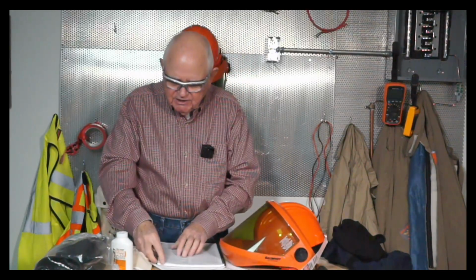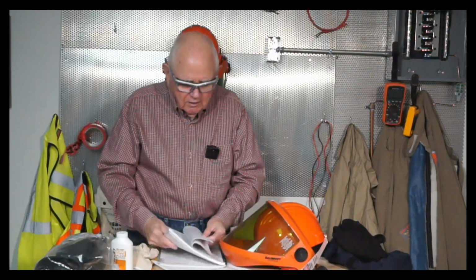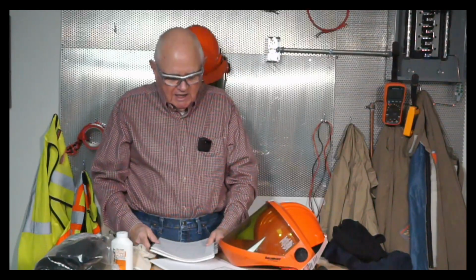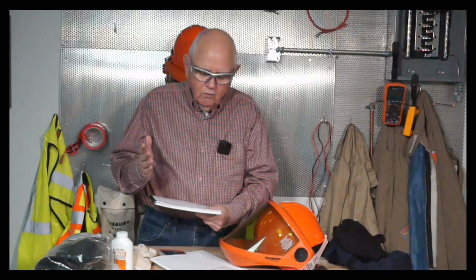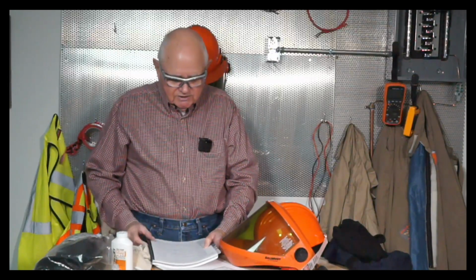Now, it goes on and gives me my other requirements for PPE. You make sure you wear your PPE based on what your electrical safety work procedure says. If I put PPE category 1 on that label, here's the confusion. To dress out for PPE category 1, I go back a few pages to table 130.7(C)(15)(c), or whatever the table is in your electrical safety work policy. It tells me for PPE category 1, my arc-rated clothing must have a minimum of 4 calories. I could wear 3.5 calorie, I don't know where you would buy that, but my clothing must have a minimum rating of 4 calories. And certainly I can buy 4 calorie rated shirts and coveralls and so on.